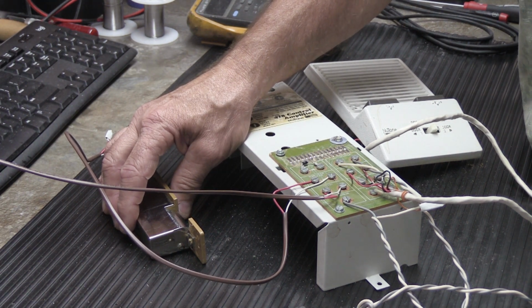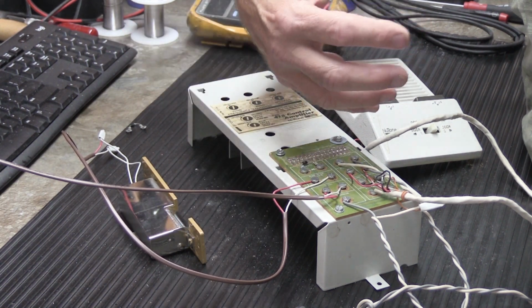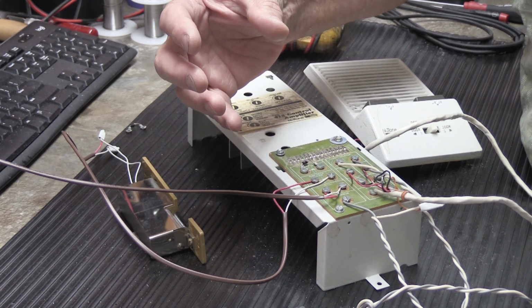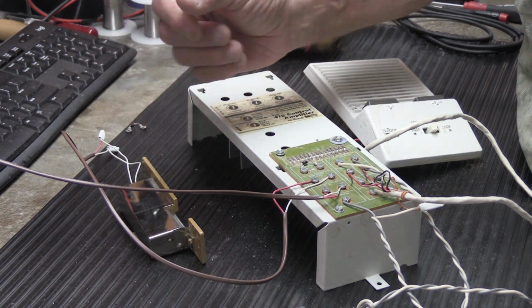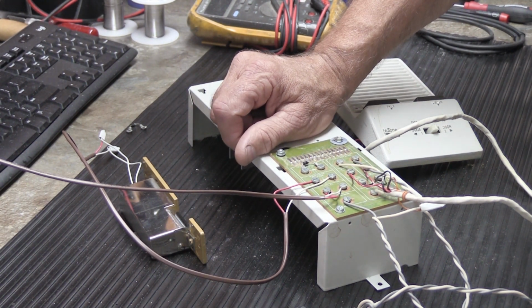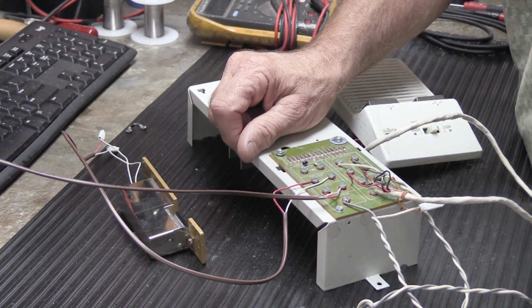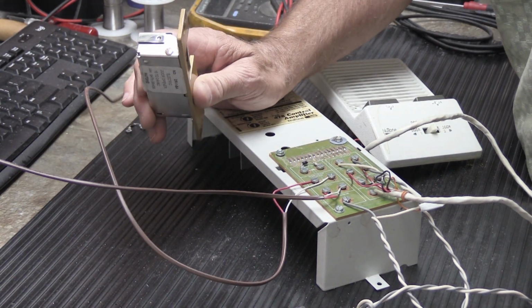And ideally, they should have some kind of hydraulic door closer on them that controls the closing of the door. It closes rather rapidly, and then the last 3 or 4 inches it slows down, and then it very carefully latches closed. That's ideal. A lot of buildings that I've been to don't have a hydraulic door closer, or it has been removed at some point, and when people come and go, they open the gate to walk out, and then they wham, slam it closed, and it basically beats the door strike to death.